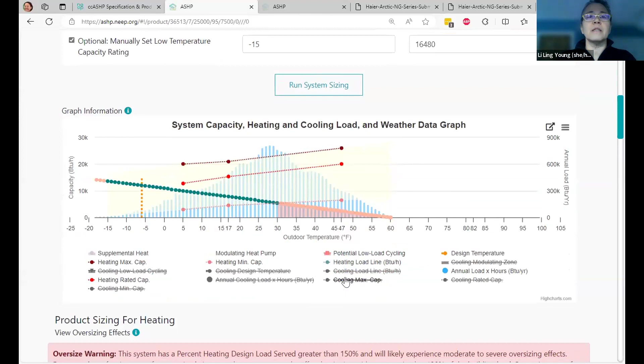You might recognize this long slope line, that's the load of the building. This vertical orange line here is the design temperature, -6 degrees, that's the location where my building is. This yellow stuff is all new, I call it a cone, the operational range of the heat pump. This upper dark red line is the maximum capacity of the heat pump at all these different temperatures. The orange line down here is the minimum capacity at those temperatures. Then there's a really unhelpful line in the middle, which is the rated capacity. I don't really care about that one, so I'm going to get rid of it.